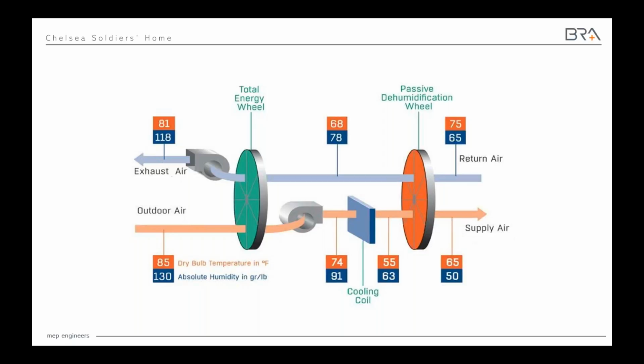At the top, you can see the exhaust air leaving and it's going through a series of two wheels. You've probably heard of enthalpy wheel heat recovery. Well, this is a dual wheel system. You get even more effective heat recovery. And then the outdoor air on the bottom is coming in from the outside through the wheel, through the coil that does additional cooling in the summer or heating in the winter, and then through the second wheel. And so in some cases, we're getting up to almost 80% effective heat recovery on these types of systems. So on a cold winter day, there's very little heat that you need to add to the air.